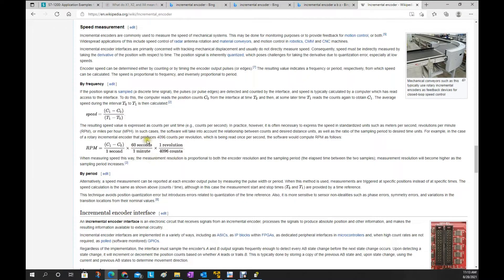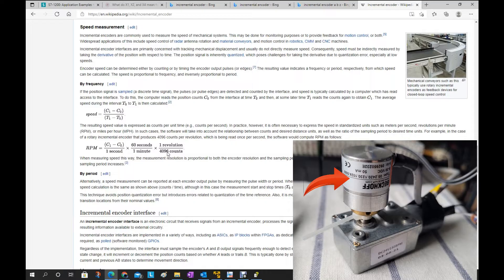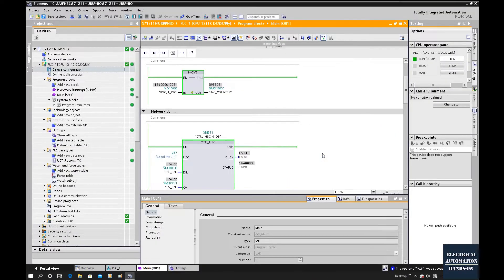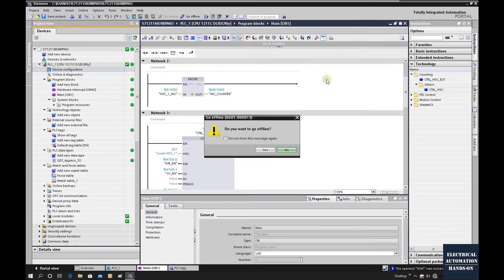We can use this equation here — we do not need to use this other area. This value here is the lines per revolution from the incremental encoder. In this case I'm using a 1024 counts-per-revolution encoder, so I need to use 1024. The difference between the first and second time sample can be captured using the cyclic interrupt OB inside the S7-1200 controller. Let's go to TIA Portal and go offline.